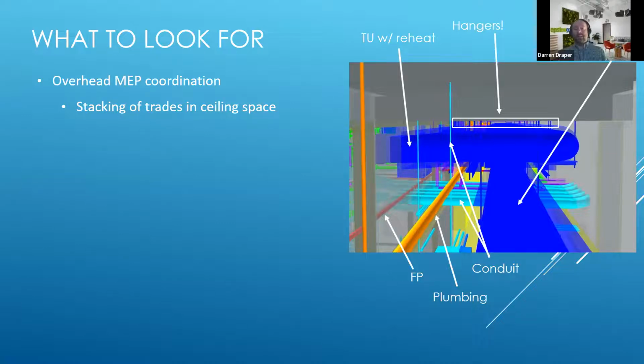And why is that important for a commissioning agent? It's not so much that everything fits, though that is important—it's that we can get back to the things we need to get back to. A terminal unit with reheat requires maintenance. A plumbing line with an isolation valve requires some maintenance. Conduit at a pull box requires the ability to access it, though the conduit itself generally doesn't. It's similar with fire protection mains—you hope not to have to get back to those too often.